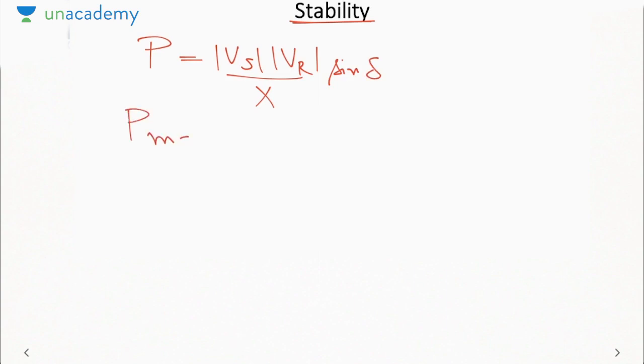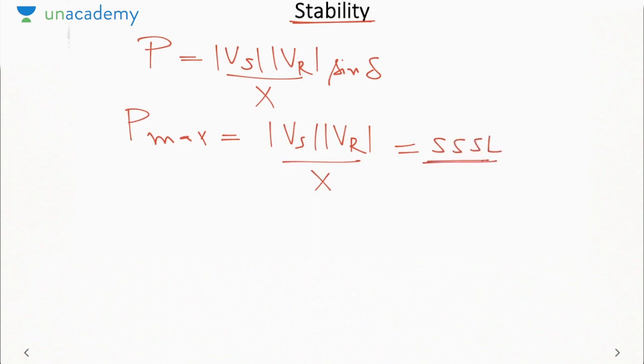Now let us see how series capacitor impacts stability. So first of all, electrical power is given by mod Vs mod Vr by X sin delta. So maximum power occurs at delta equal to 90, and it is equal to mod Vs mod Vr by X. This is also called as steady state stability limit. Okay, means if you try to draw more power than this, then the system will become unstable. That is the maximum power that can be drawn from a system. Okay. So higher the maximum power or higher the steady state limit, more stable the system will be.